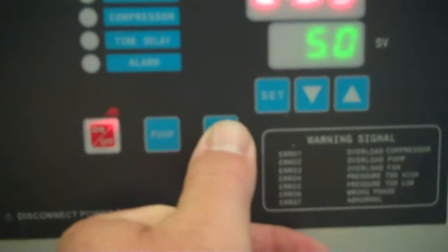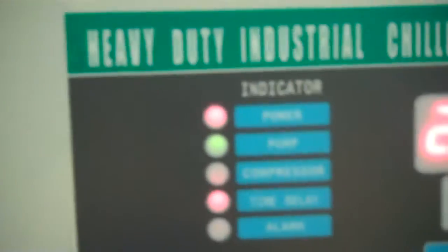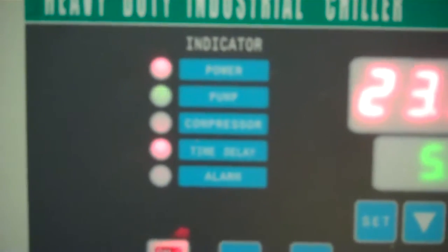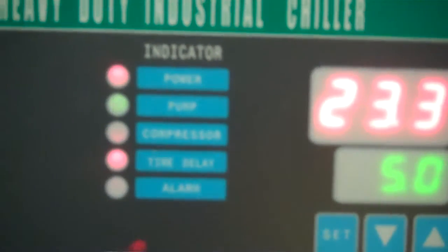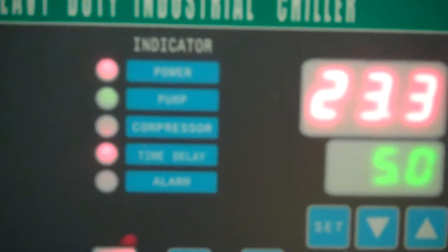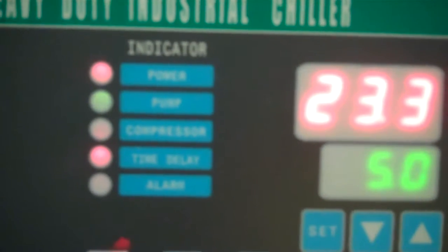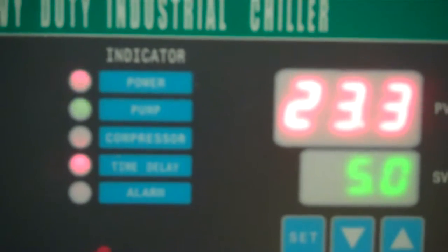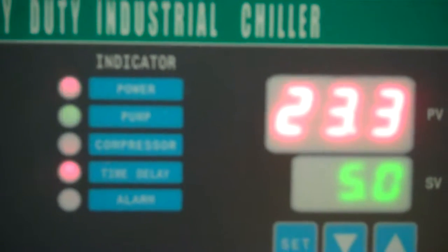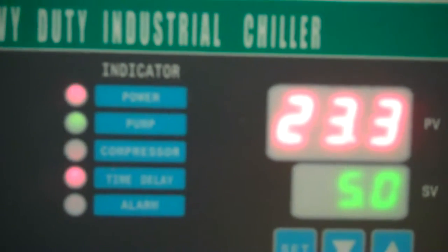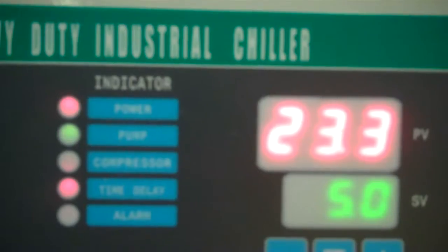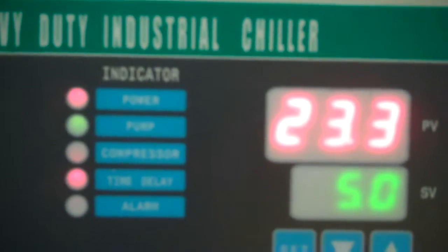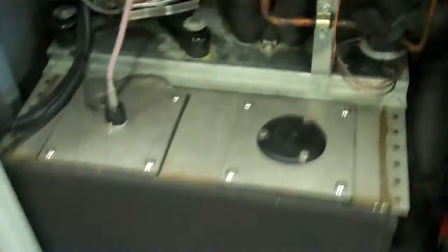Then what we do is we press the compressor button. When we do that, a little time delay comes on. It might be 90 seconds, it might be just under 2 minutes before it's going to allow the compressor to turn on. That's just a built-in safety to avoid short cycling of the system and to avoid too frequent starts and stops of the compressor.